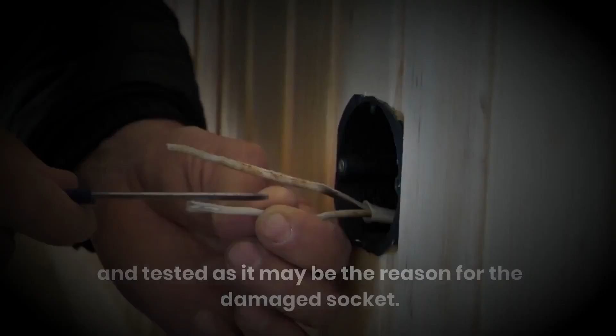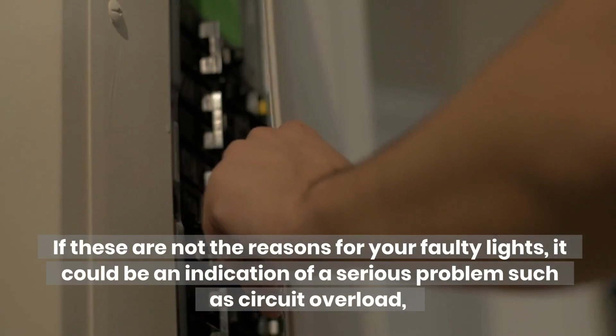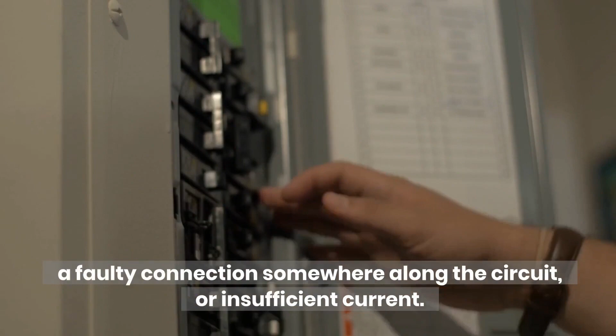Faulty lights. Flickering, dimming, or buzzing lights can be more of a hindrance rather than an electrical safety issue. These issues are often ignored due to their commonality. For the most part, the solutions can be straightforward: loose light bulbs, bulb type, or weather. If these are not the reasons for your faulty lights, it could be an indication of a serious problem such as circuit overload, a faulty connection somewhere along the circuit, or insufficient current.